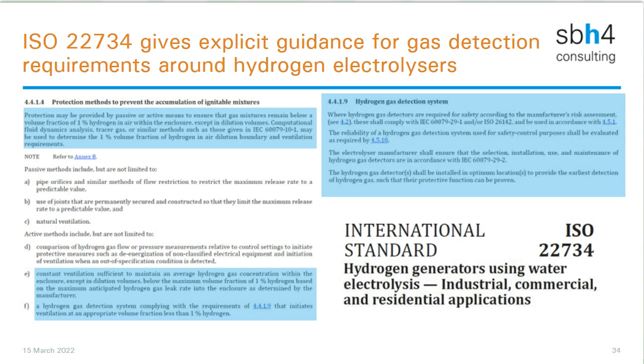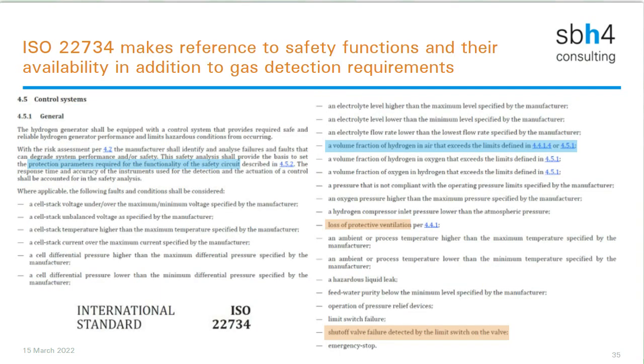That standard makes reference specifically to safety functions and their availability, in addition to gas detection requirements. So the gas detection device would ultimately need to operate a safety function. For example, turn on some ventilation. And that safety function itself, the ventilator, the fan, we would also need to understand that that is operating or available to operate as required.